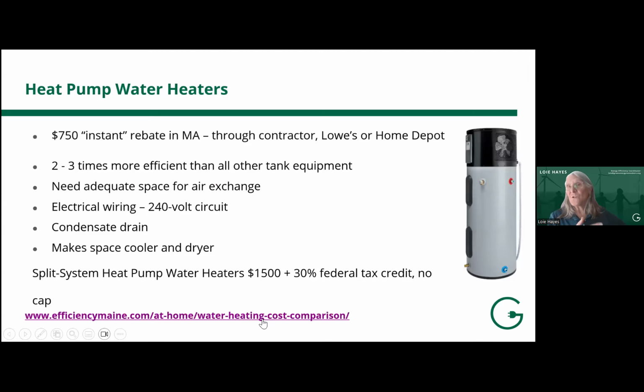Heat pump water heaters: for those with a boiler with indirect water heating connected to it, you'd need to figure out what to do for hot water heat. There's an incentive for heat pump water heaters. This is the hybrid model, where the heat pump sits right above the storage tank. These are 2 to 3 times more efficient than other tank equipment. You need adequate space for the air exchange—you don't put this in a small utility closet. It needs a 240-volt circuit, a condensate drain, and it will make that basement space cooler as well as drier.